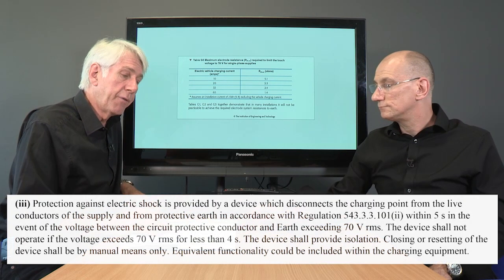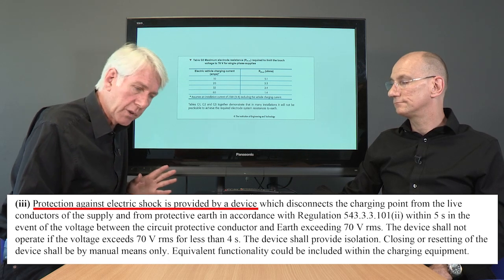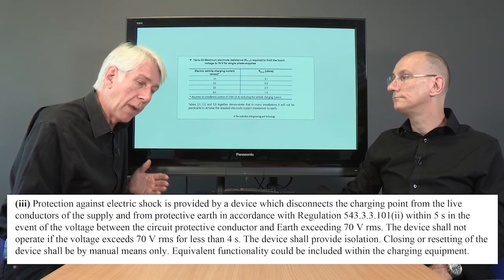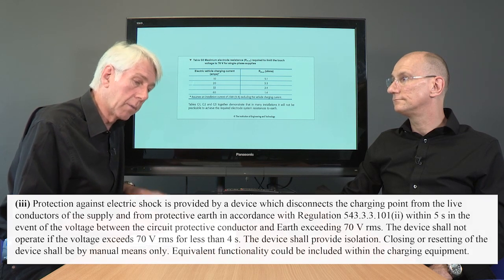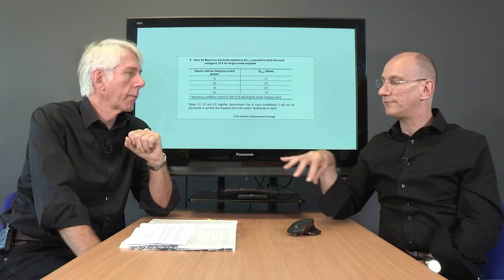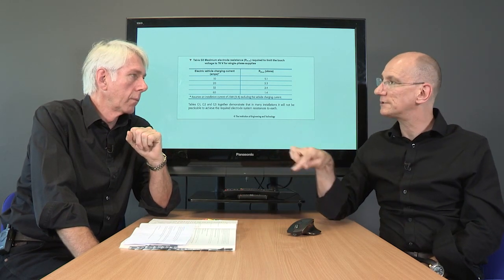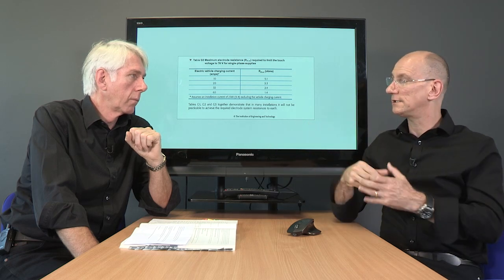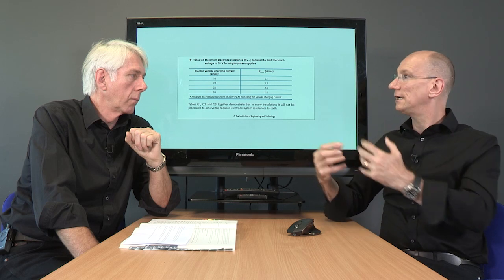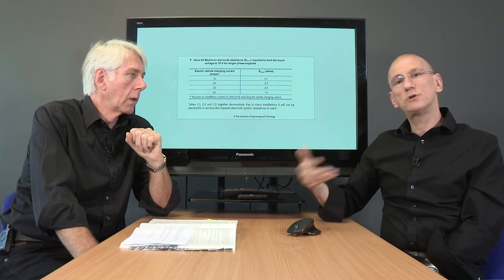So the third one was this: a device providing protection against electric shock which disconnects the charging point from the live conductors of the supply and from protective earth, in accordance with regulation 543.3.3.101. Read it yourself. Yeah, I mean, we sort of touched on that in the last video, Dave, where the device didn't exist, and it was in Amendment 3 as well, so it was pre that one. Amendment 2 it came out, but it never existed in the hope, and it was all about numbers and who would be able to manufacture this and get it into circulation and use. Now, through innovation and entrepreneurship, there are a number of individuals and organisations that have been working with this. I'm not going to say it complies with all of the requirements of that one, but from what I can see and have read on the internet, it certainly has a lot of technical ability to make things safer, and we need to watch this space.